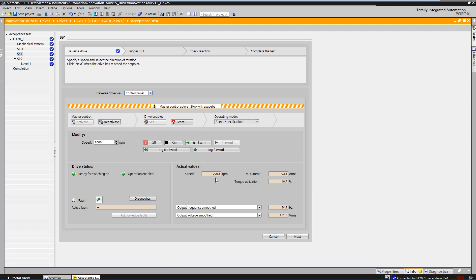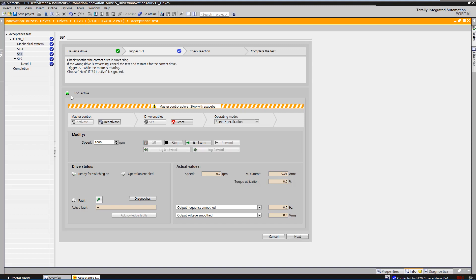The actual values show that the drive has reached the speed. Via Next, you can switch to the next step. Check here whether the correct motor is rotating. After checking that the correct axis is rotating, we select SS1. The LED shows that SS1 is now active.